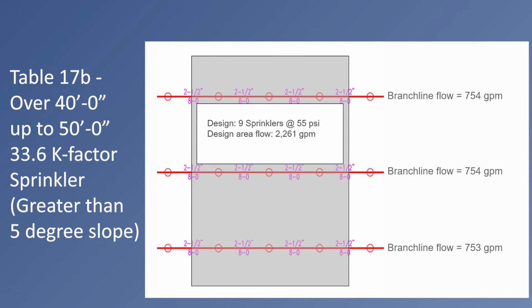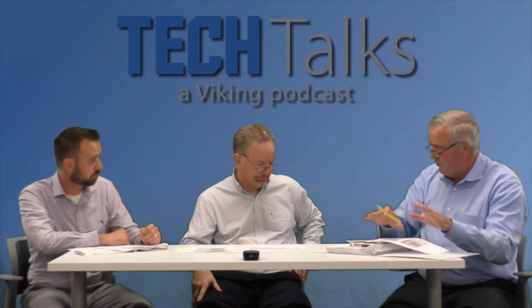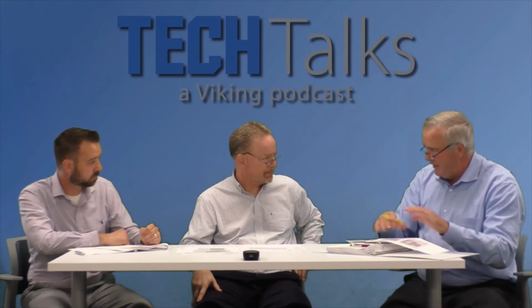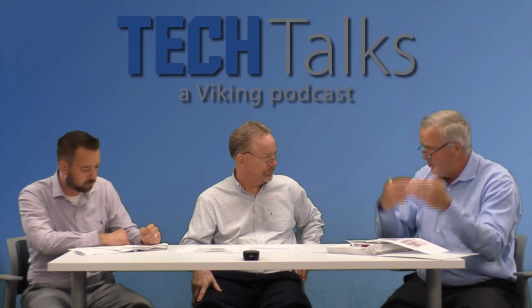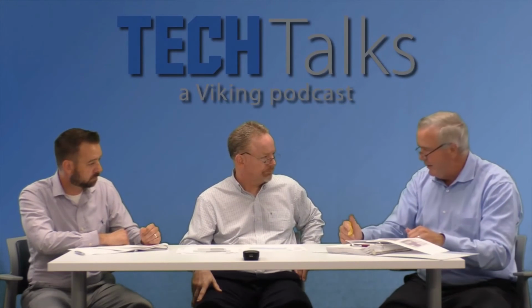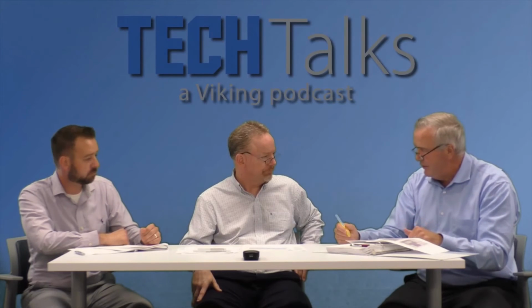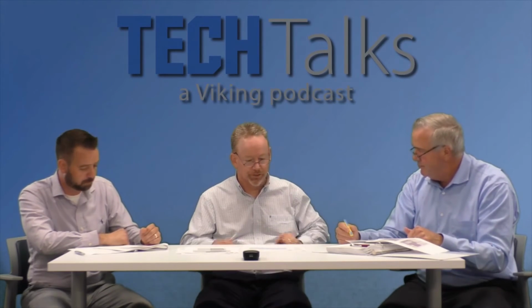And keep in mind that these two examples that Shaun has just walked you through are all above 40 foot, to 50-foot design protocol, now mandatory for ceiling-only protection for FM. This is all 6-foot aisles, so there's no difference of any aisle spacing at the 50-foot level. So it's all like product that this hydraulics is being compared to. Yeah, that's a good catch right there.